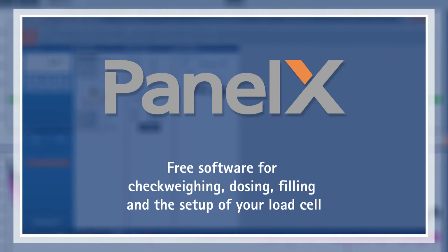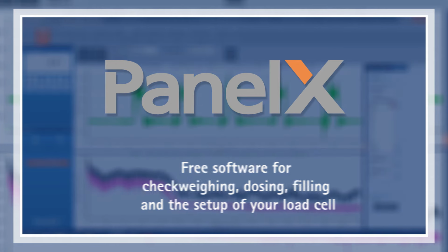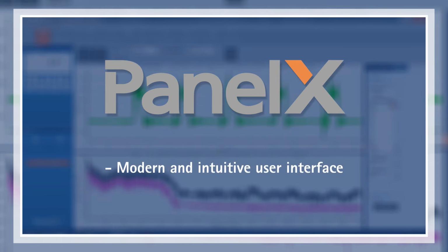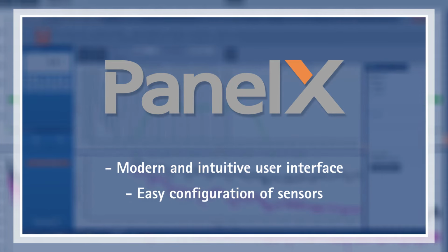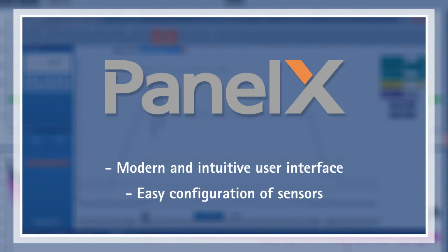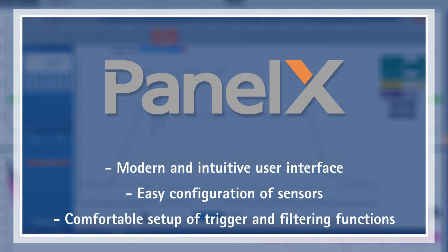HBM offers the free software Panel X for use with Checkweighers, dosing applications, and for diagnostics. Follow the necessary steps for the configuration of the Checkweigher via the Panel X software. These include the configuration of sensor electronics for the real-time processing of raw signals or the setup of trigger signals and the setting of limit signals.